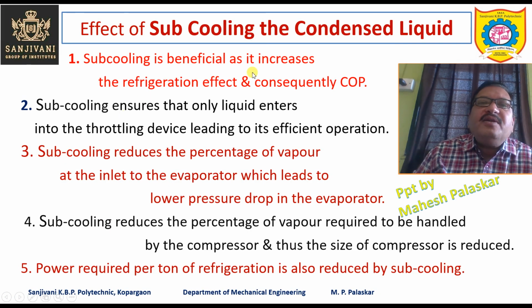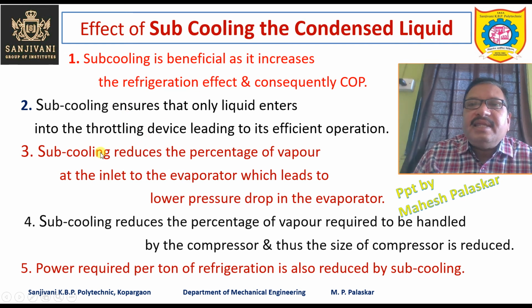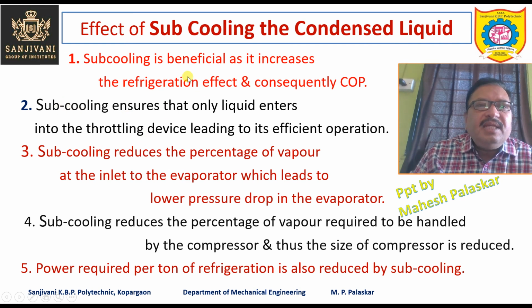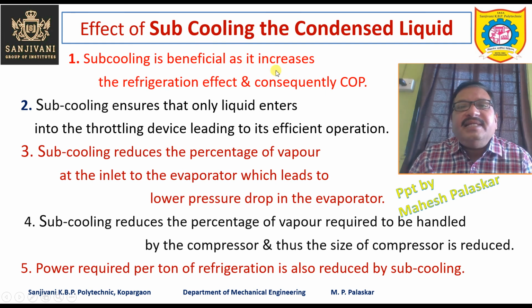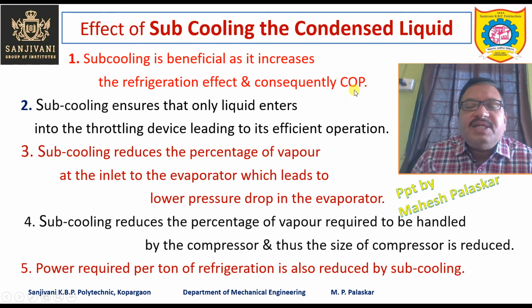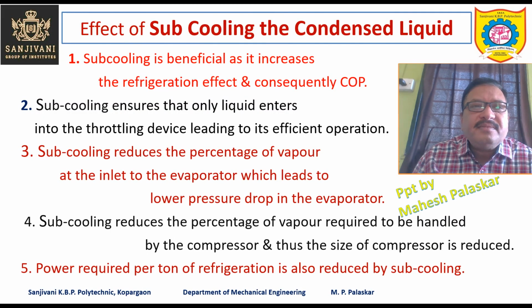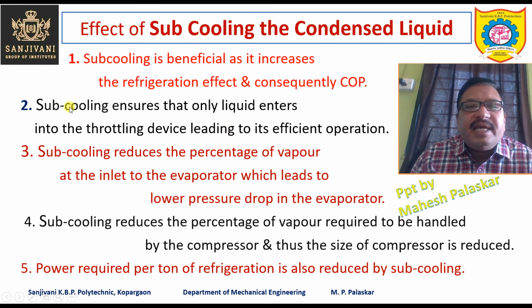So what are the effects of subcooling the condensed liquid that we have to see? Now this subcooling is beneficial as it increases the refrigerating effect and consequently COP. The refrigerating effect is increased, we have seen how, and consequently the COP is also increased due to subcooling. Subcooling ensures that only liquid enters into the throttling device, leading to its efficient operation.